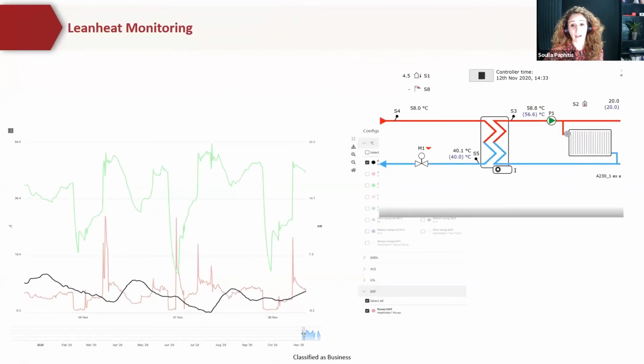So just to show you how, looking at weather compensation when you're looking at your substation and heat exchanger is really, really important. And it's something that should be taken into consideration when you're looking at how you're controlling your substation. So as you can see on this graph, and it is quite small, so apologies if you can't see it properly, but on this chart, the green line is showing you the flow temperature from the secondary flow, and the brown line is showing you the heat meter power in instant kilowatt. So the weather compensator is saying that if the outside temperature drops, there is an increase in the kilowatt demand and the flow temperature. And when the outside temperature rises, there is less demand for power and temperature.